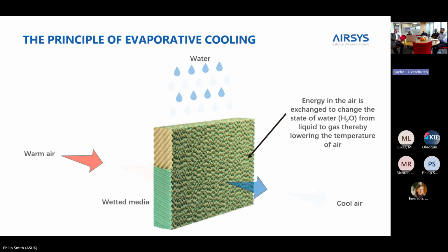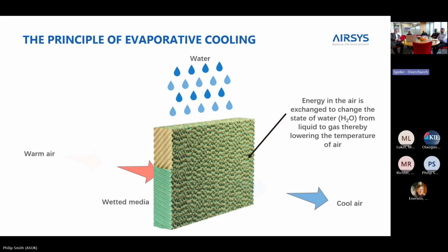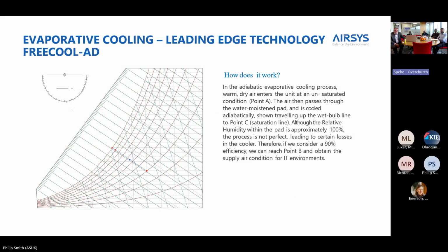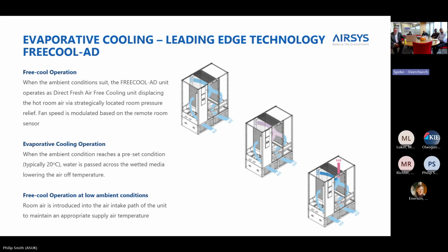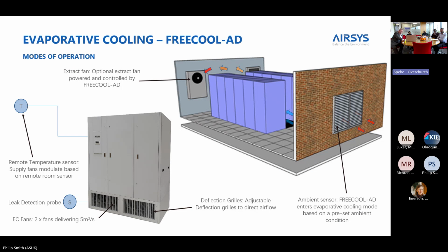In terms of efficiency, it's very good. We'll get up to 80–90% RH off it. It works well in hot environments as well, obviously. In terms of the psychrometric principle, we are adiabatically cooling up the wet bulb line to approach the saturation line, but not completely. In terms of the operation, again similar to the other units you saw, we are bringing fresh air in and cooling it via the pad, or recirculating air and mixing it as required. This particular sort of product would sit inside the room. You've seen the earlier example with the CRAC unit, with air in and air extracted.